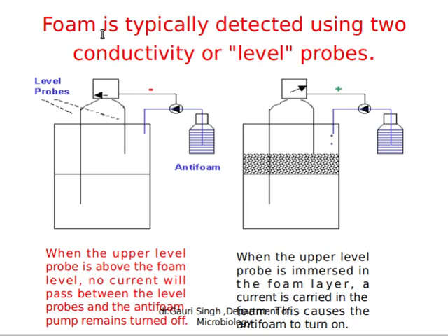In this picture, foam is typically detected using two conductivity or level probes. When the upper level probe is above the foam level, as in this picture, there is no foam generation. So no current will pass between the level probes, and the anti-foaming pump remains turned off.